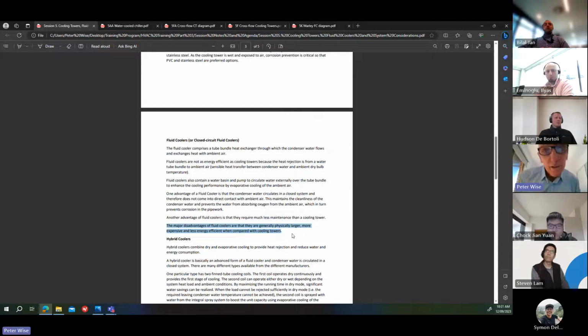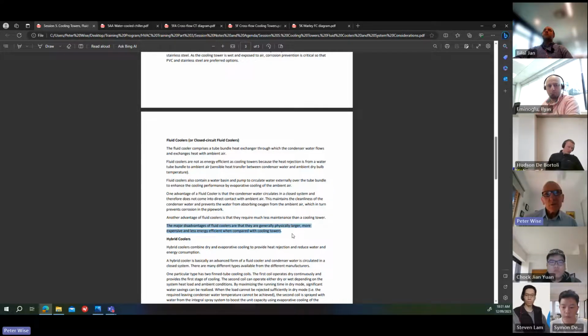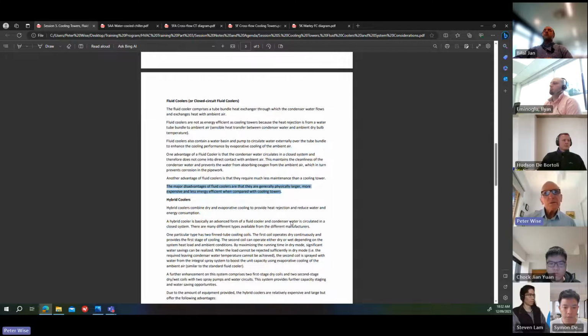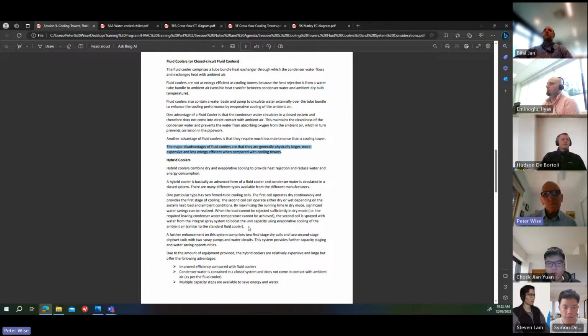If you're doing a water-cooled VRF system, I know that some manufacturers won't guarantee the units if you're using cooling towers unless you have a primary secondary system. So your cooling tower water would have to go through another heat exchanger, and then on the clean side of the heat exchanger, you'll go through your VRF condensers. Some other manufacturers don't mind, but it's really to do with build-up or fouling of the heat exchanger, the condenser in the VRF condenser. So just be aware of that as well, because if you need to have a secondary system, they'll have more pumps, heat exchangers, more controls, and so on.